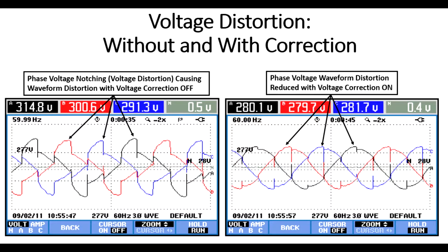With the voltage correction on, everything operated cooler and quieter and significantly more efficient, not having to handle all of that current that was trying to get rid of the current from the electrical noise called harmonics. The power transformer itself had to power all of the load. It had to supply the power to that power filter that was being pulled to ground and dissipated as well. That's no longer a problem. The power transformer runs cool. The factory runs more efficiently, and there is much rejoicing.